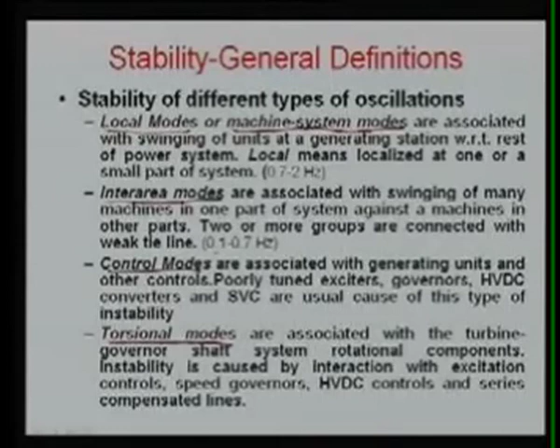Another one is your inter-area modes. Inter-area modes of oscillations are associated with the swinging of many machines in one part of the system against the machines in another part of the system, where two or more groups are connected with a weak tie line, and this oscillation is normally 0.1 to 0.7 hertz.